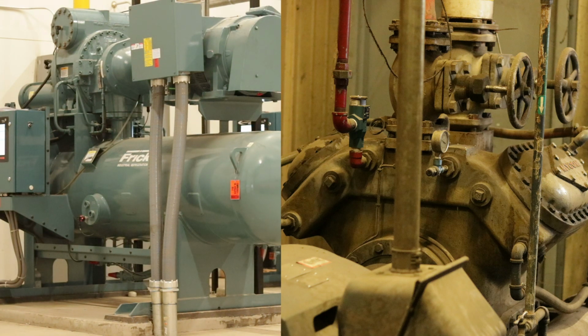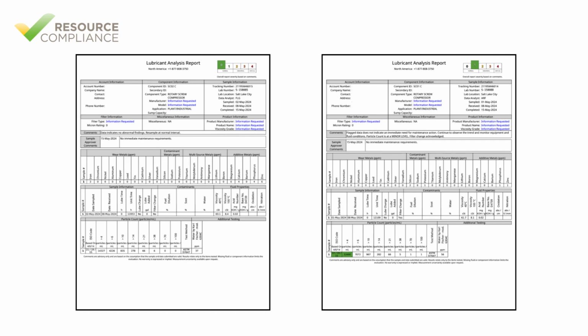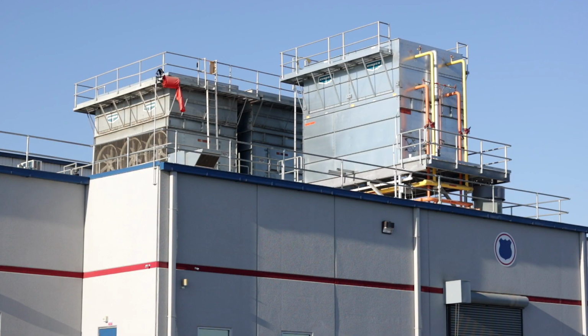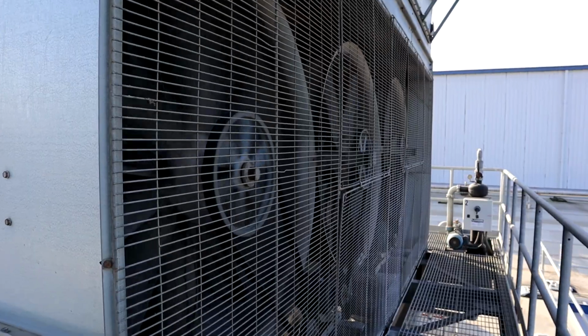For example, the quantity of oil in a reciprocating compressor is substantially less than that of a screw compressor. Therefore, replacing the oil annually on a reciprocating compressor, which is an example of preventative maintenance, may be employed while oil analysis, a form of predictive maintenance, is done on the screw compressors only. For inexpensive, low-risk items, reactive maintenance may still be used in a reliability-centered maintenance program.